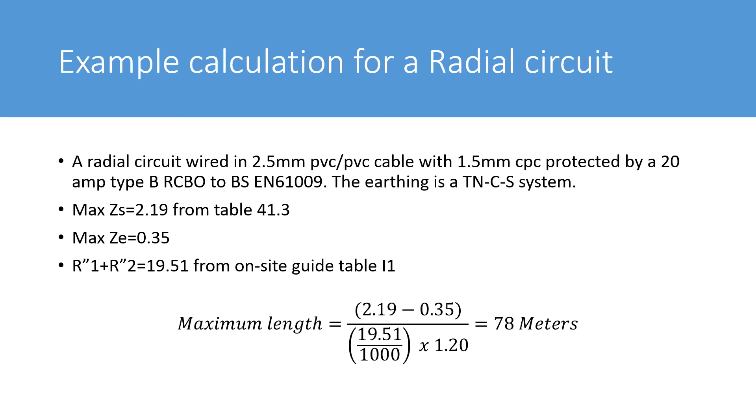So the maximum ZS would be 2.19 and that's from table 41.3. The maximum ZE is going to be 0.35 for a PME system. And the tabulated values for R1-R2 is 19.51 milli-ohms per meter. And that's from the on-site guide table I1.